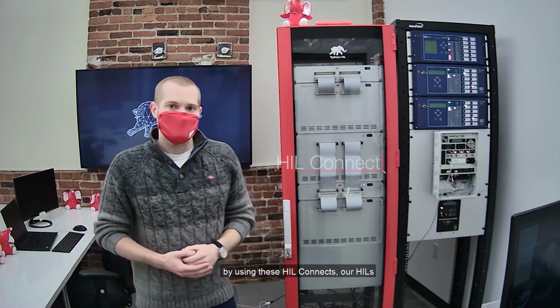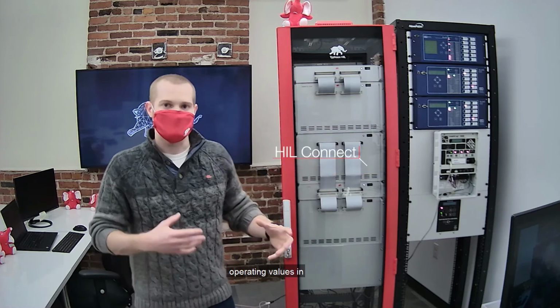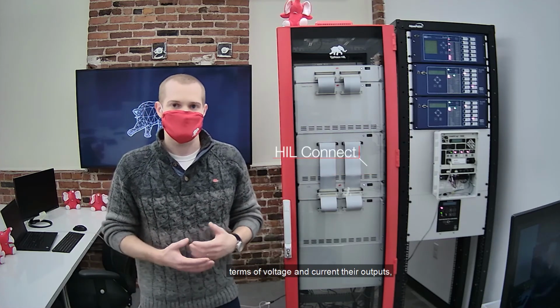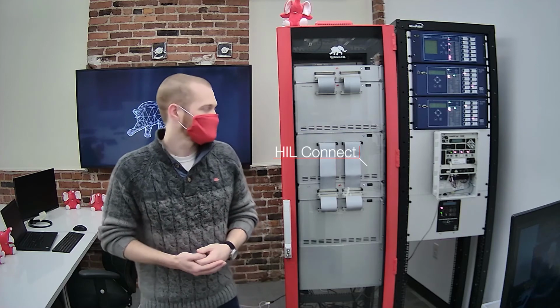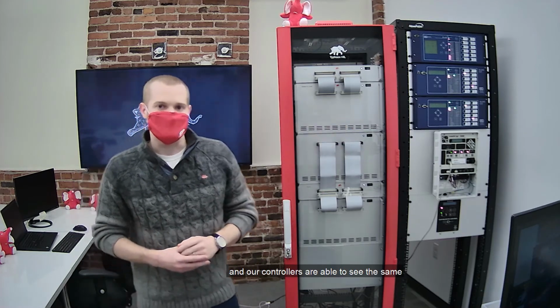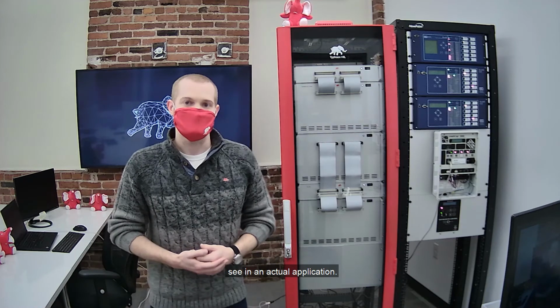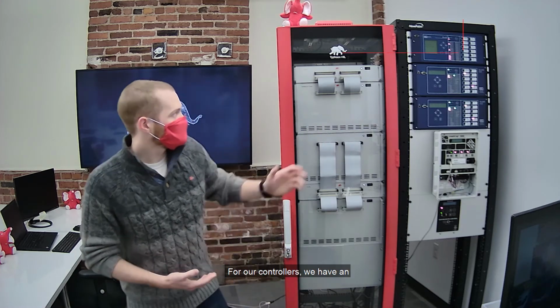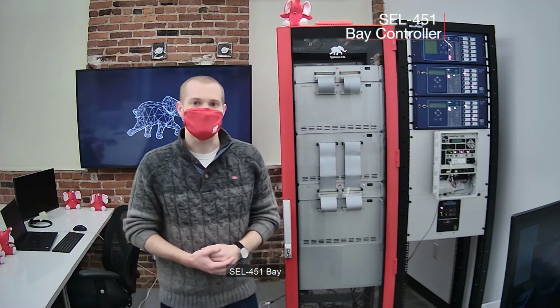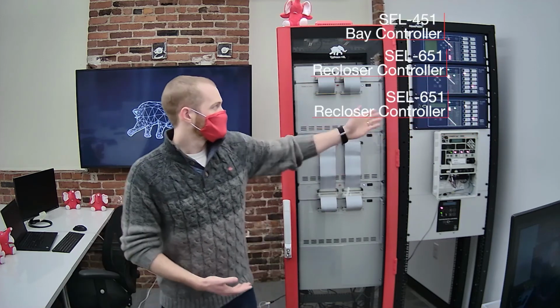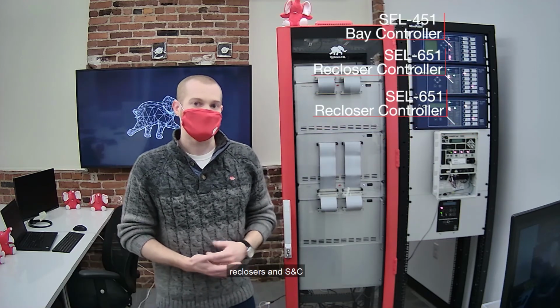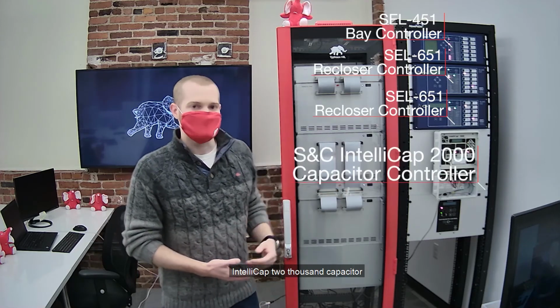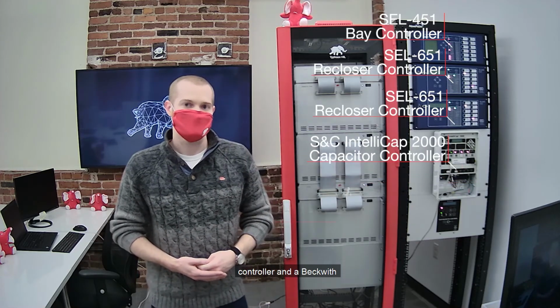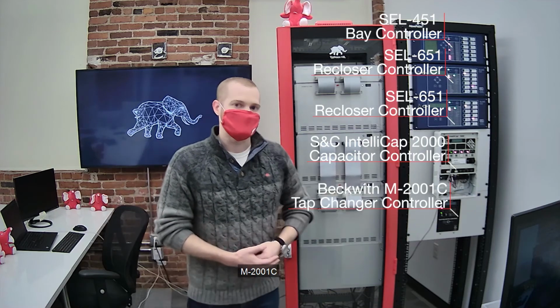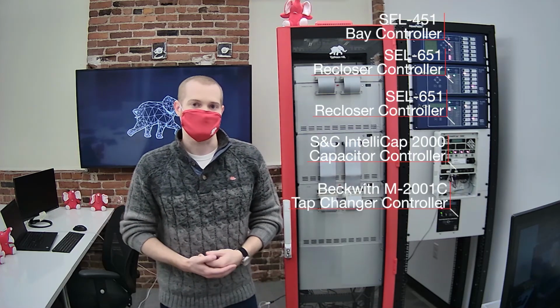By using these HIL Connects, our HILs are able to keep safe operating values in terms of voltage and current at their outputs, and our controllers are able to see the same voltage and current levels they expect to see in an actual application. For our controllers, we have an SEL 451 Bay controller, two SEL 651 reclosers, an S&C IntelliCap 2000 capacitor controller, and a Beckwith M2001C tap changer controller.